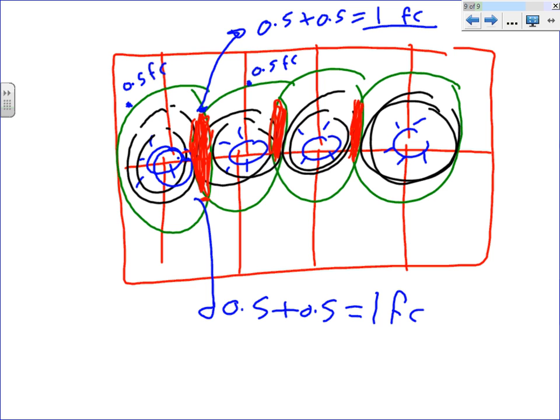Why do you think I didn't make this one 2 in a parking lot? 2 is too much light in the parking lot. 0.5 is your cutoff, meaning I'm guaranteed that everything within this green circle is 0.5 or more. Anything further away is actually less than 0.5, which I care less about in my design.